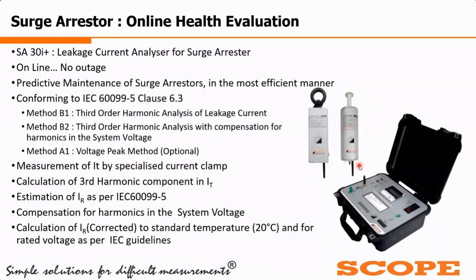And then we are doing the estimation of IR as per IEC 60099-5. And finally, we also have an inbuilt temperature probe in the instrument, so we are measuring the ambient temperature at the time of measurement of this leakage current. So we can automatically calculate the IR corrected. The instrument will give you the automatically calculated IR corrected value as per the IEC standard factors, whatever they have given.